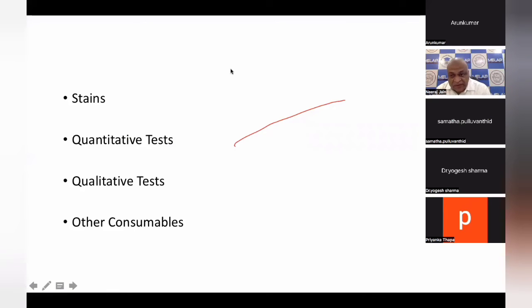Other consumables, what are these other consumables? Like your syringe, if it is a 5 ml syringe, how are you accepting it? It should measure 5 ml only. In one tube, take 5 ml with some other already accepted syringe and transfer that volume into the tube. In another tube, transfer with the new syringe which you want to approve. See whether the volume is the same or not. Then whether you are able to generate vacuum in that syringe or not.